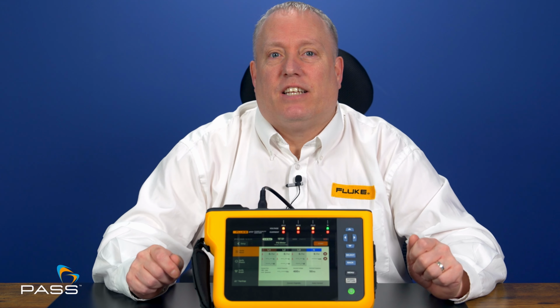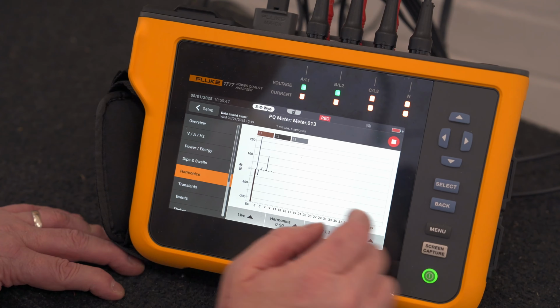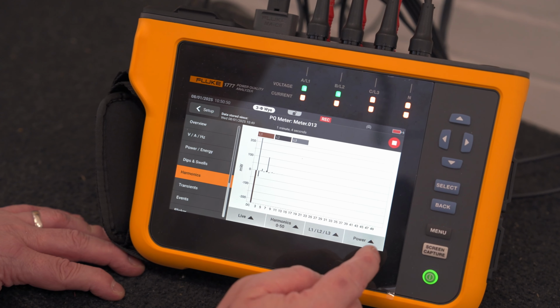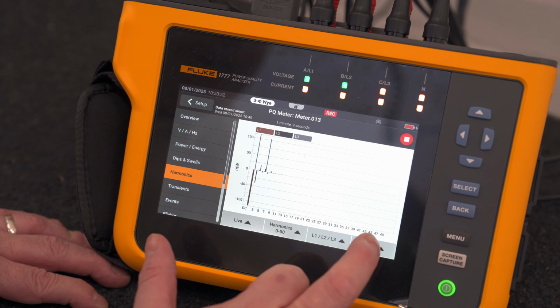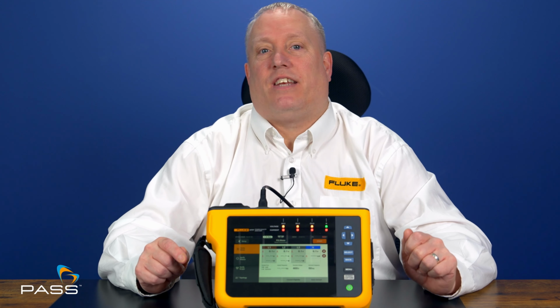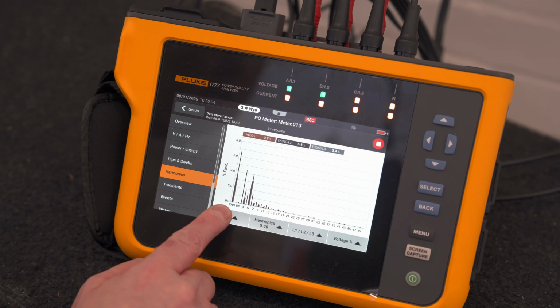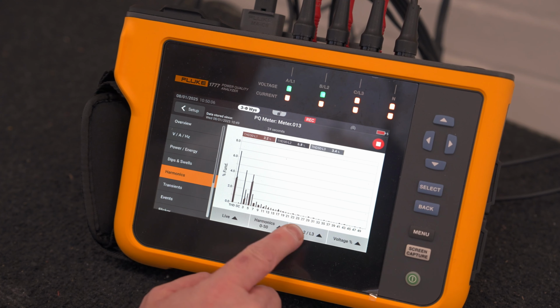Harmonics are the silent killers of power quality. They distort your electrical waveform, leading to inefficiencies, equipment failure, and yes, even more wasted energy. Using the Fluke Analyzer, you can identify harmonics in seconds—it gives you total harmonic distortion, pinpointing exactly where the issues lie.